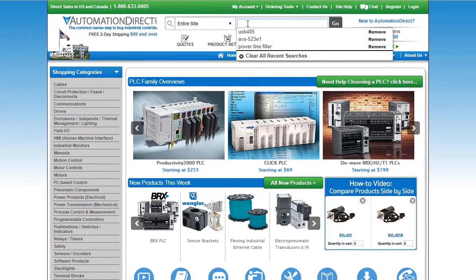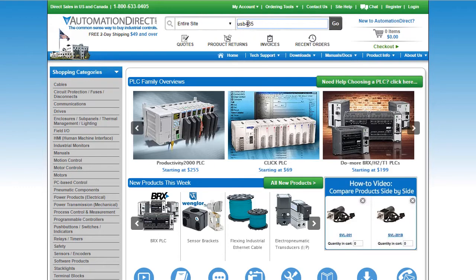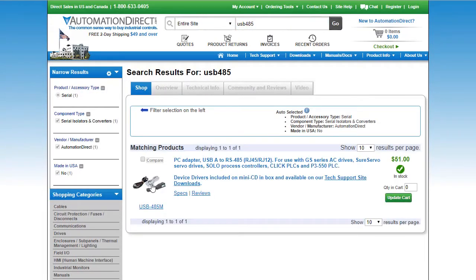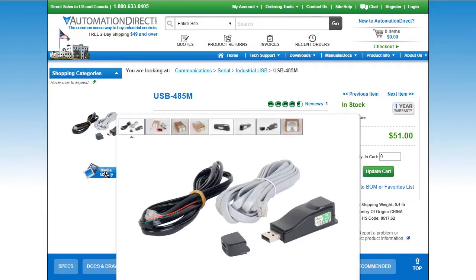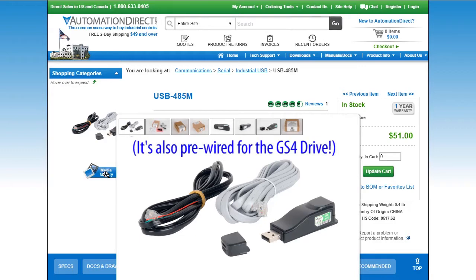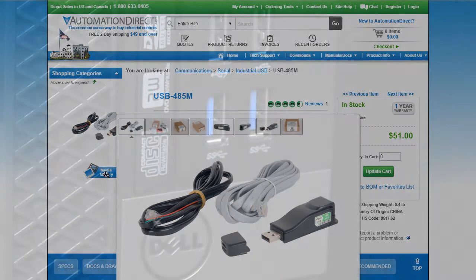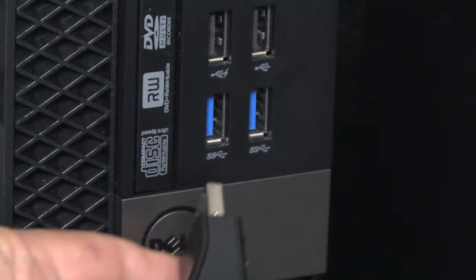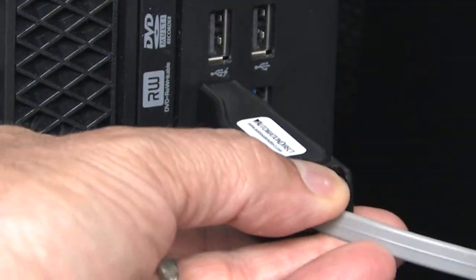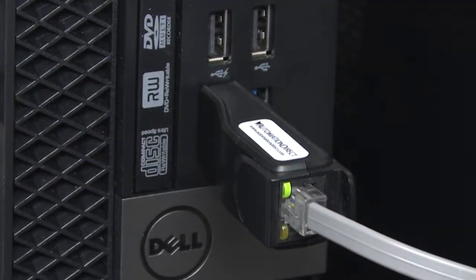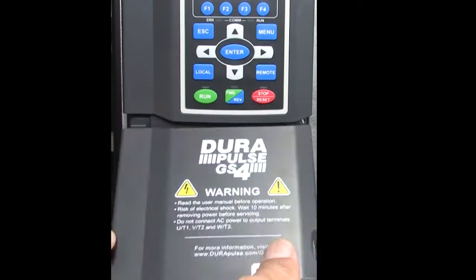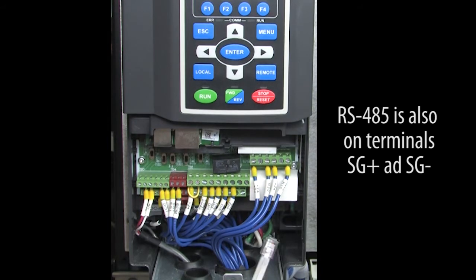Next you'll need a USB to 485 converter. This is the recommended converter because it's the one AutomationDirect's support team is familiar with. If you use some other converter, they may not be able to help you if you need to contact them. Plug the USB adapter into the PC and the other end into either of the RS-485 ports on the drive.